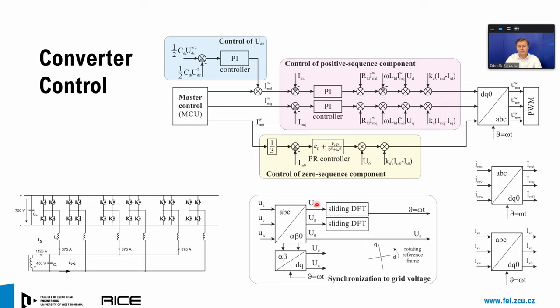A few words about the control. We have several control modes. The positive sequence components are controlled in the rotating reference frame DQ, which is linked with the grid voltage, while the zero sequence component is controlled by a proportional resonant controller. We have two master control loops. The first one is the control of the DC link of our converter, which commands the active component of the positive sequence current. The second master control is responsible for the generation of the reactive component of the positive sequence component in case the STATCOM functionality is demanded. The master control is also responsible for the generation of the compensation current command.